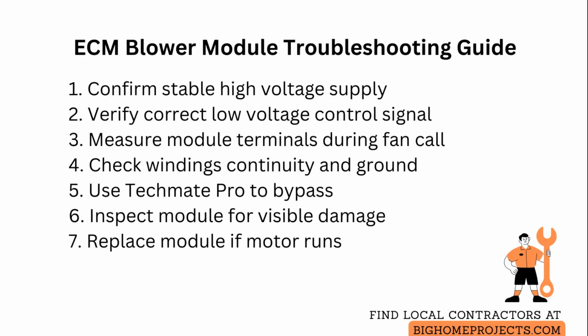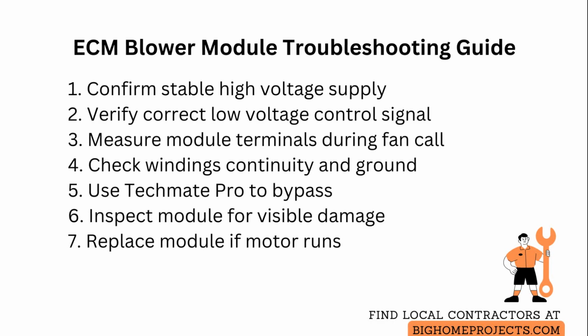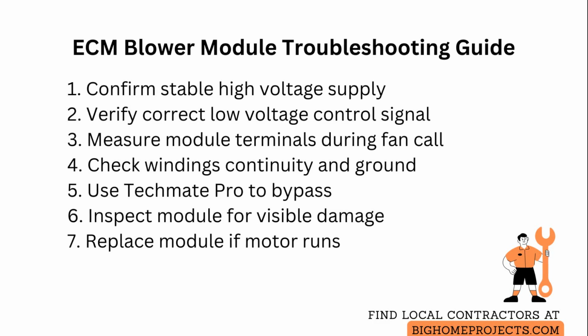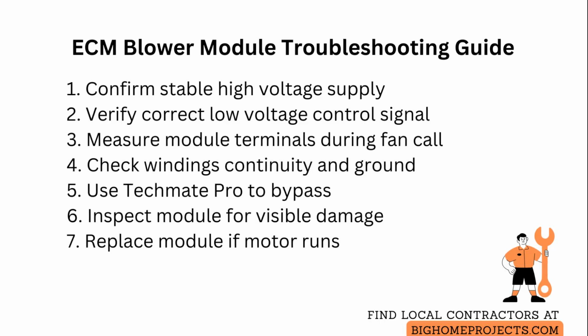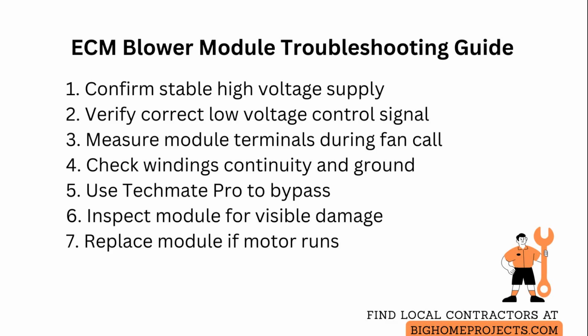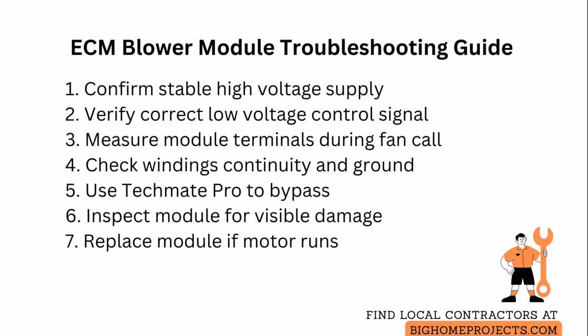Check motor windings for continuity and verify there is no short to ground by measuring resistance from each winding lead to chassis. An open winding or any connection to ground indicates a bad motor. Use a Techmate Pro or equivalent to temporarily bypass the control module and drive the motor directly from a known good power source to see if the motor runs smoothly at full and reduced speeds.